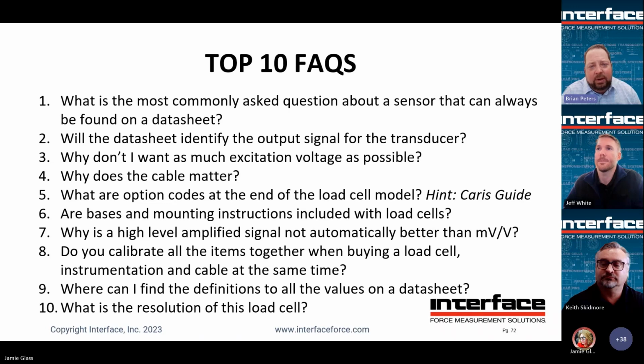All right, are bases and mounting instructions included with load cells? Bases, usually if it's an LP, you'll need to specify. The part number becomes a -B. We always recommend bases. That'll help give you your best chance of hitting the specifications of the datasheet. You can still use it without a base. Again, we want to make sure that there's adequate hardness of the mounting surface, and then 2/10,000ths total flatness, as was mentioned earlier. That's what we test ours to, and we can't guarantee performance or meeting spec without. So it's always best. Bases make it a lot easier just to hook up the low profiles as well.